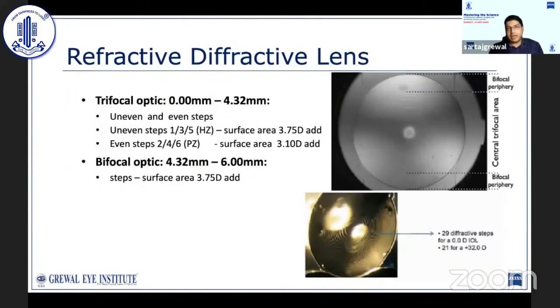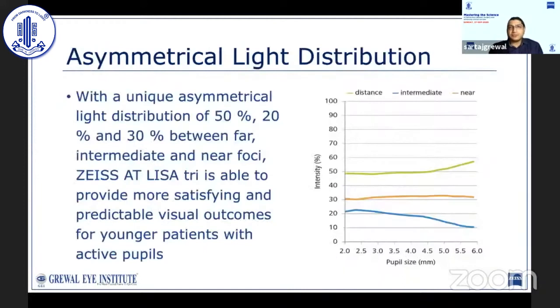Phase shifting zones are the junction between two adjacent diffractive steps. Through a unique manufacturing process, the phase zones of the AT-LISA are machined such that they do not have any right angles, significantly helping reduce light scattering. The AT-LISA is a refractive-diffractive IOL, where out of the total 6mm diffractive zone, only the central 4.32mm are trifocal, and the outer 2mm region of the lens sends light to the far and near foci exclusively. So in scotopic situations, where an apodized bifocal IOL would begin to lose out on near vision, the AT-LISA loses out on intermediate vision but still does not compromise near vision. The lens distributes 50% of light for distance, 20% for intermediate vision, and 30% for near, and the distribution for intermediate vision falls once the pupil enlarges beyond 4.3mm.